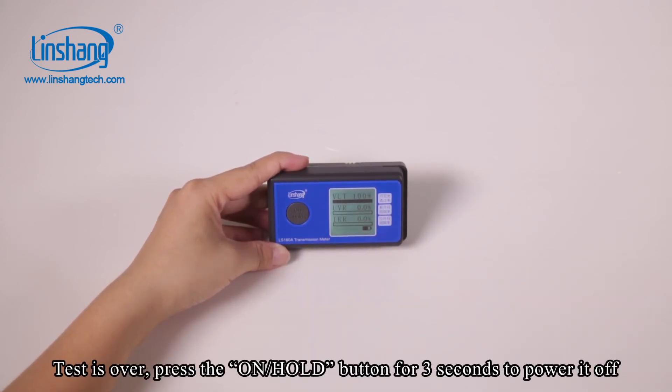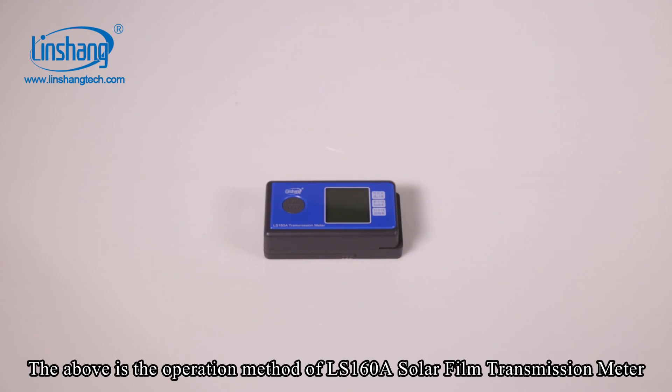When the test is over, press the hold button for 3 seconds to power it off. It will also shut down automatically without any operation in 3 minutes. The above is the operation method of the Linshang LS-160A solar film transmission meter.